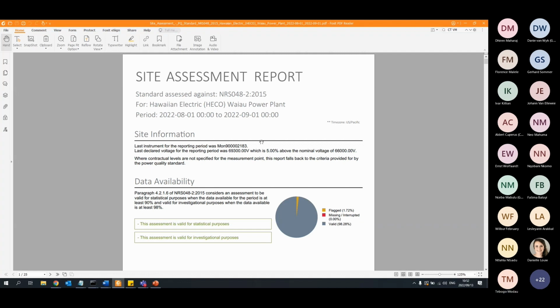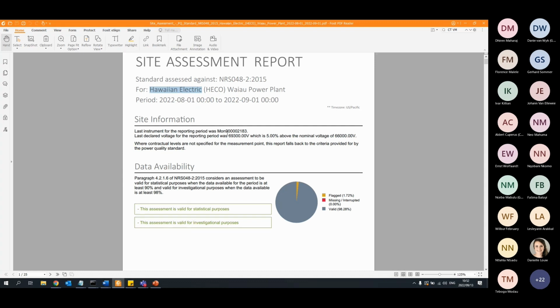Thank you. So here we have an example of a site assessment report that I pulled from our Osprey Pro system. You all are probably familiar with that. We also covered Osprey Pro, and there were 2 sessions specifically on that. So this was for a measurement point with the name Hawaiian Electric. It's a power plant for the period of 1 August to 1 September 2022. So it's a month period that we used for the assessment. We can see, very important as I said in the beginning, that the declared voltage here is set to 69,300, which is 5% above your nominal voltage, which is 66,000.